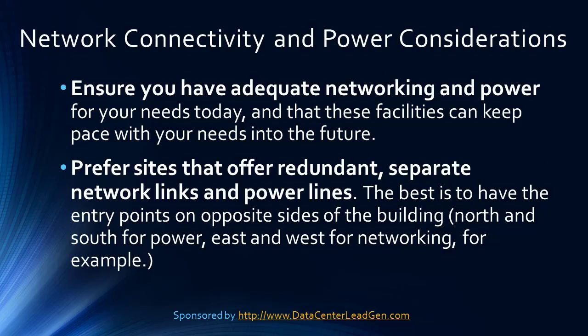Network Connectivity and Power Considerations: Network connectivity and power availability must be properly assessed. Ensure you have adequate networking and power for your needs today, and that these facilities can keep pace with your needs in the future. Prefer sites that offer redundant, separate network links and power lines. The best is to have entry points on opposite ends of the building — north and south for power, east and west for networking, for example.